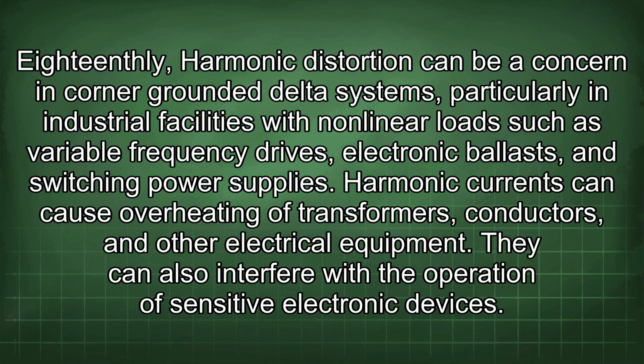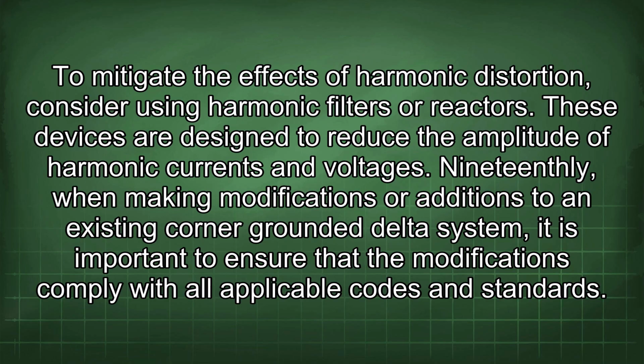Harmonic currents can cause overheating of transformers, conductors, and other electrical equipment. They can also interfere with the operation of sensitive electronic devices. To mitigate the effects of harmonic distortion, consider using harmonic filters or reactors. These devices are designed to reduce the amplitude of harmonic currents and voltages.